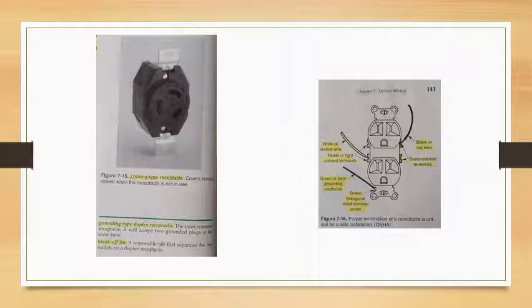Non-grounding receptacle. The non-grounding receptacle shown in figure 7-13 is installed in older houses that do not have any grounding. You must not install a standard grounding receptacle as a replacement for a non-grounding receptacle unless you are going to upgrade the wiring system to include a grounding path. You should not install a non-grounding receptacle in a house that is grounded. These receptacles do not accept three-pronged plugs, which may limit the receptacles used to lamps and radios. Section 406.3-D-3 describes the accepted methods of replacing a non-grounding type receptacle.